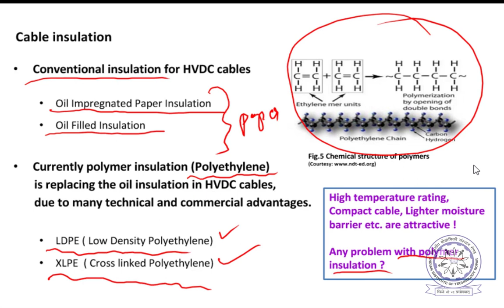So is there any problem with this polymeric insulation? Let us see what happened. Here, there was a cable laid during the 1970s between Hokkaido, the northern island, and Honshu, the mainland. So there is a cable link here. They used this polymeric insulation, cross-linked polyethylene. The old oil impregnated paper cable was replaced by this polymeric insulation cable.